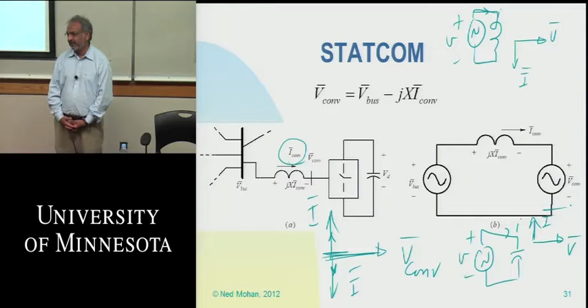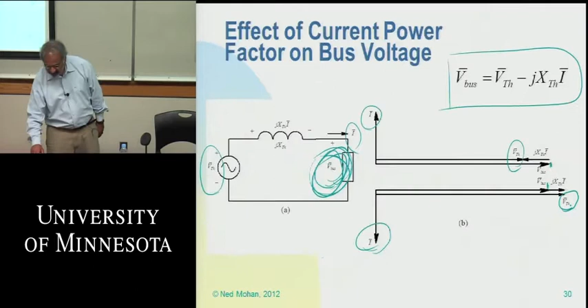This power electronic device, StatCom, can control whether you're drawing leading or lagging current, so in one case you draw reactive power, in the other you supply it. That makes a difference in power factor, and therefore in the voltage we see.